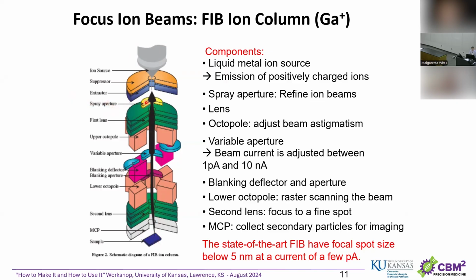Here you have the aperture. An aperture is nothing more than a small hole, because we don't want those ion beams to spread. We just want a focused beam, so we put a small hole here. Then here we have the lenses, the green ones: the first lens and the second lens. This is not an optical lens, it's an electromagnetic lens. Simply speaking, because ions are positively charged, you apply a certain negative voltage so that you can either attract or repel those ions from the lens. The goal is to have a really focused ion beam. So here we have the first lens.